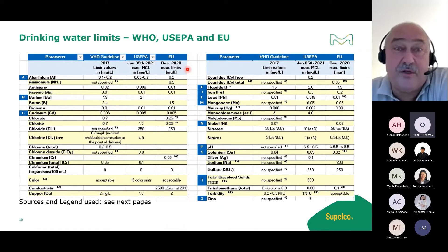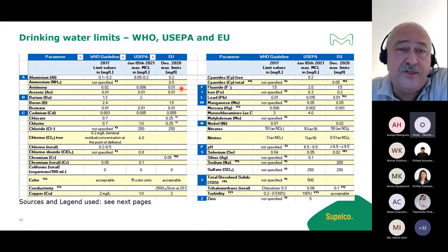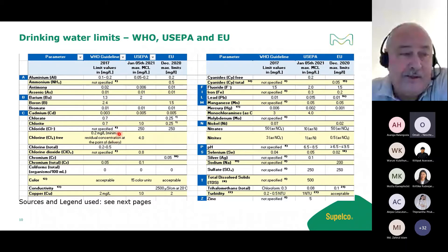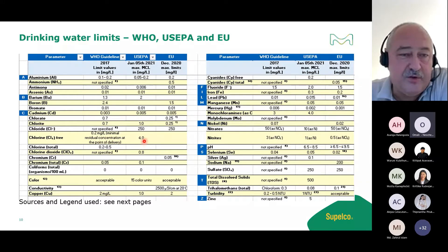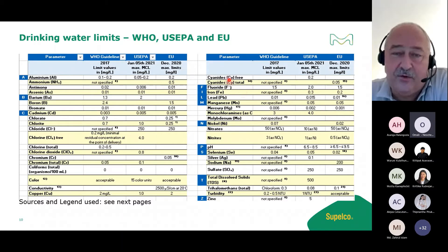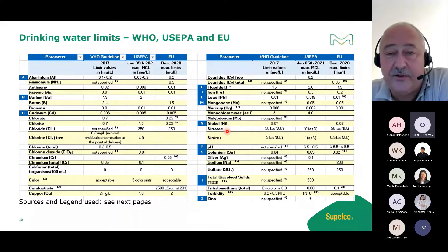Looking at the comparison table, I've made a short extract of the WHO guideline, US EPA limits, and EU limits - the EU directive being the largest update from December 2020. Key drinking water parameters include aluminium, ammonium, bromate at 0.01 mg/L, chlorine typically at 0.2 to 4 mg/L, chromium, copper, cyanide, iron, manganese, nitrate, and nitrite.